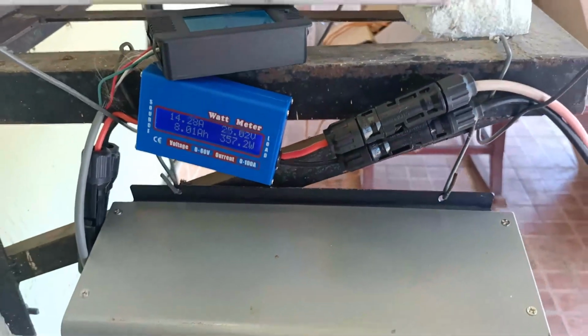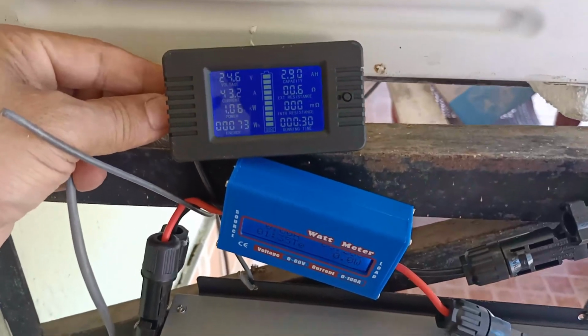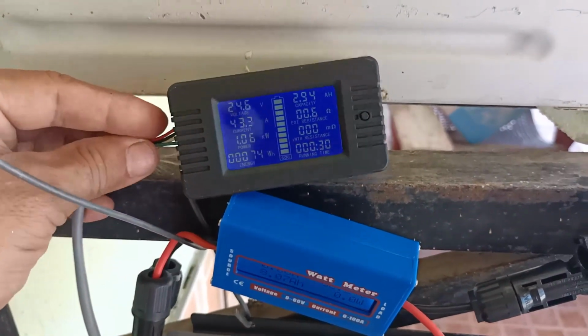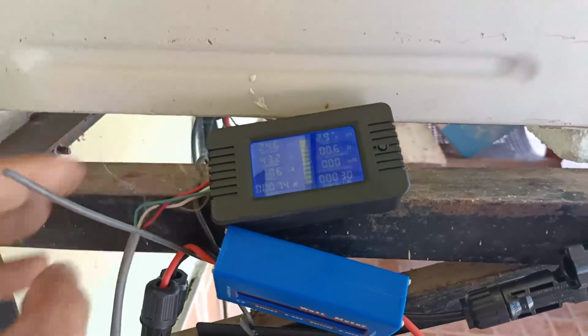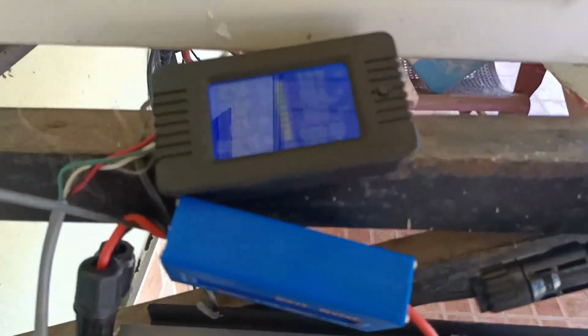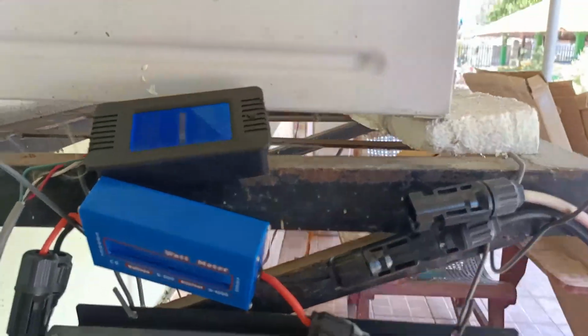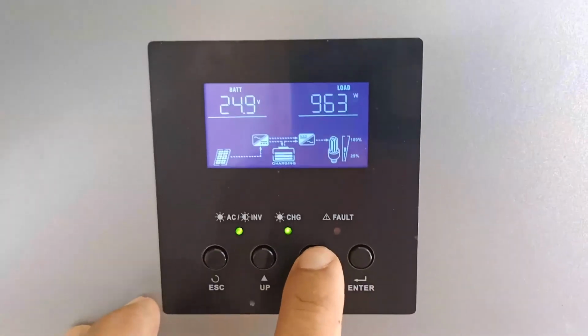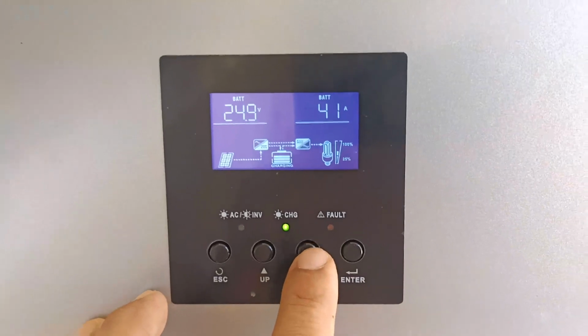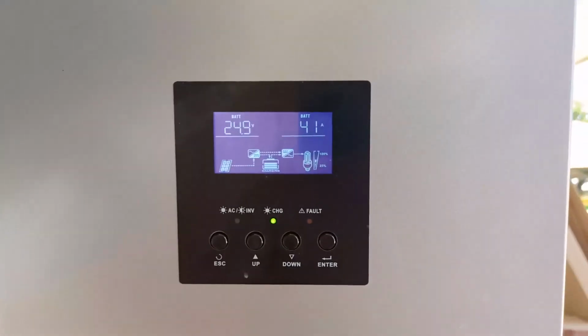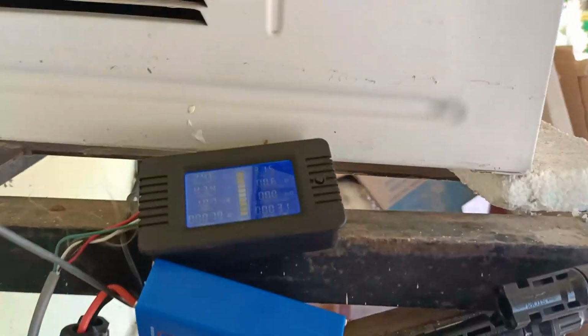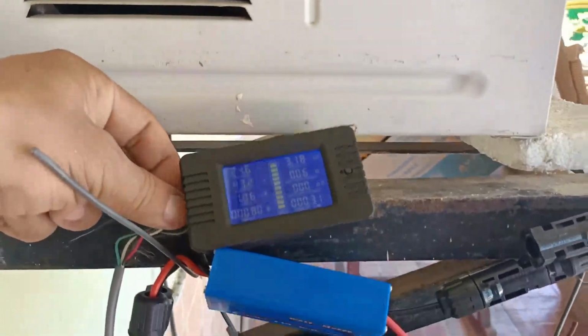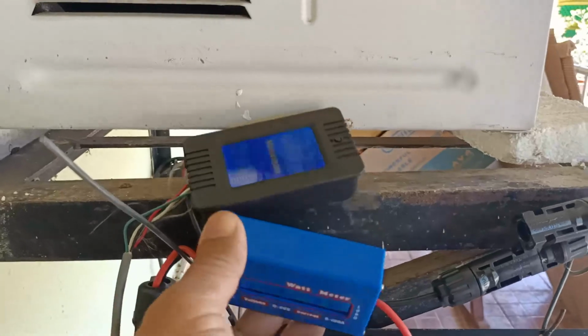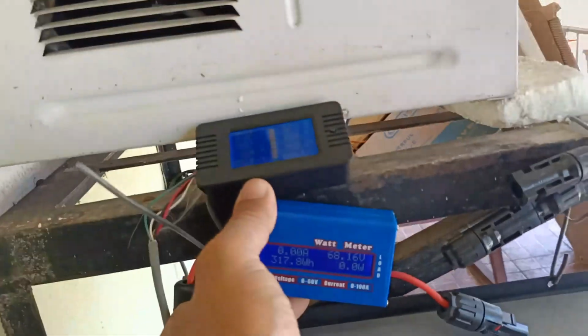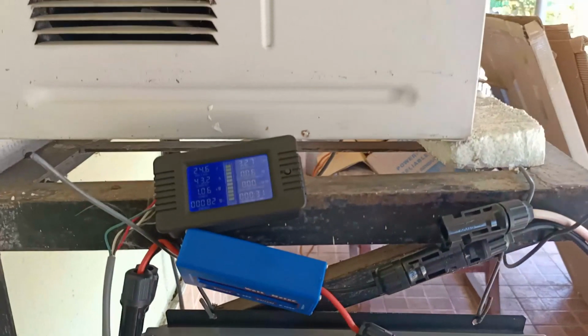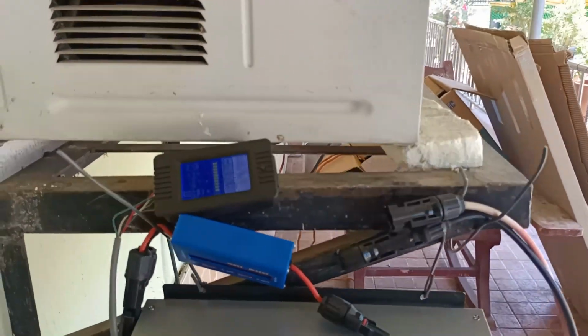So I'll do that. I removed the solar share. Now everything is coming out of the battery. It's 43 amps on that meter, and 41 amps on the inverter. So it doesn't matter. When you're sucking current like that, it's irrelevant whether it's off by 2 or 3. So this thing is working.